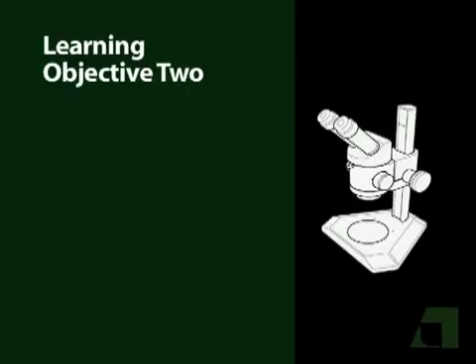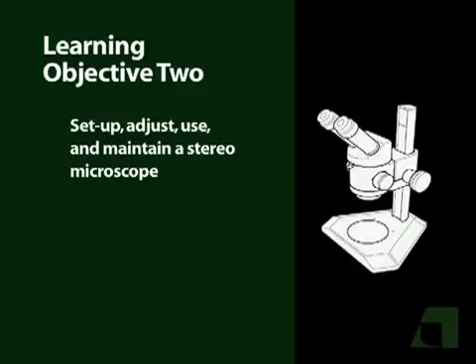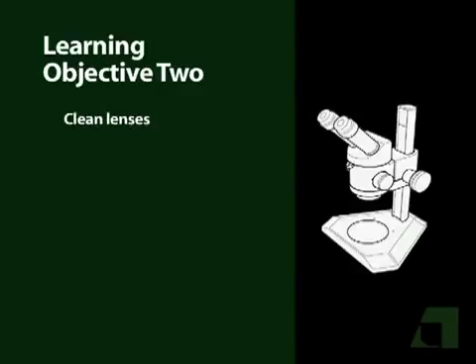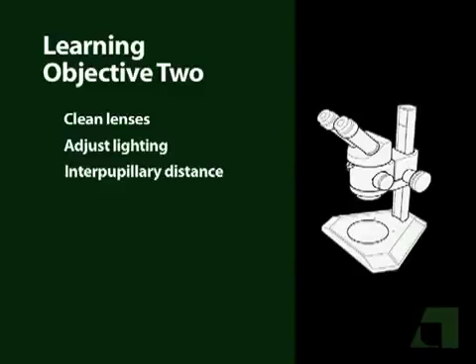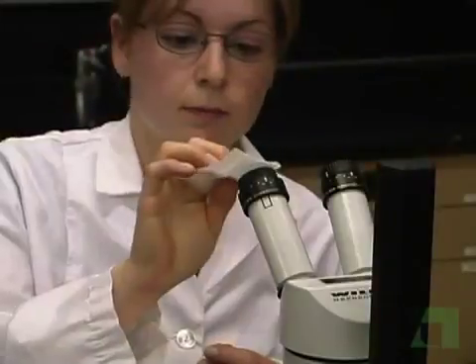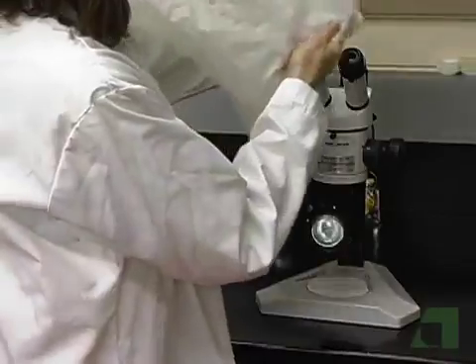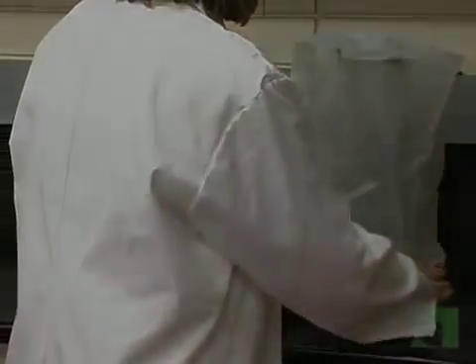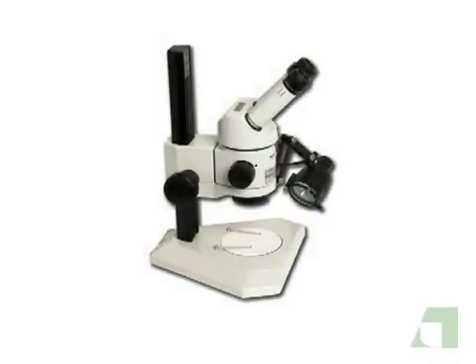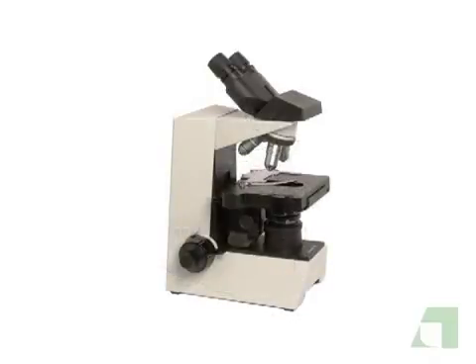The learning objective of this section was to set up, adjust, and use a stereo microscope. This included cleaning the external surfaces of ocular and objective lenses, adjusting the light, adjusting interpupillary distance, setting diopter adjustment, and focusing. Be sure to clean your ocular lenses and replace the dust cover before storing your microscope. The major disadvantage of stereo microscopes is that they are normally limited to magnifications of about 50 times. For higher magnifications, you have to use a compound microscope.